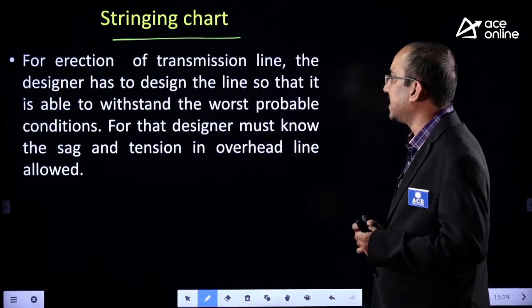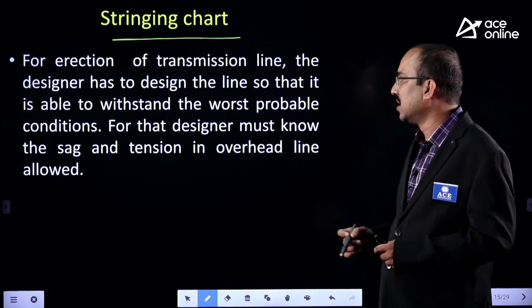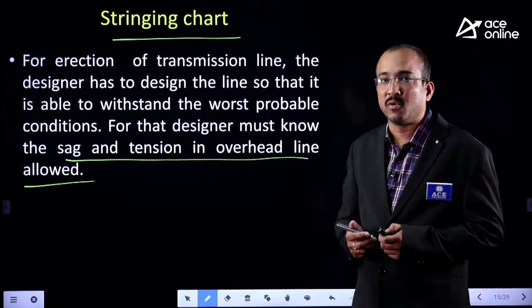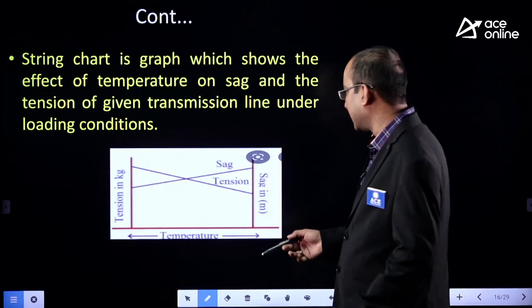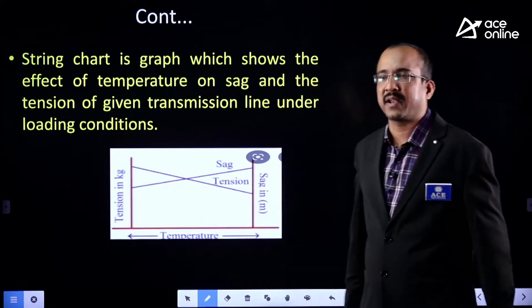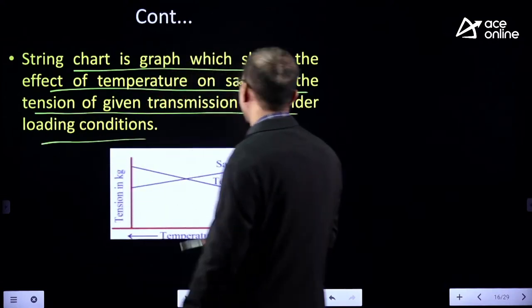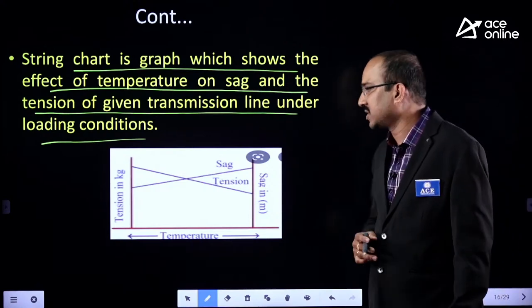What do you mean by a stringing chart? For erection of a transmission line, the designer must know the SAG and tension that can be allowed in an overhead transmission line. A stringing chart is a graph which shows the effect of temperature on SAG and tension of a given transmission line under loading conditions.